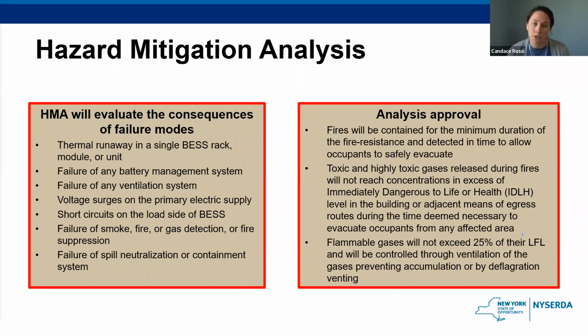So here we have the hazard mitigation analysis, which is only required for energy storage technologies that were not listed in that initial scope, when more than one technology is provided in a room or enclosed area, or where allowed as a basis for increasing the maximum allowable quantities. So we'll get into that in a few slides. But basically, any lithium ion system over 600 kilowatt hours will be required to perform this analysis. So this study is done to evaluate the consequences of failure modes. These are usually done by an engineering firm for the town to determine the best approach on how to handle a failure. The analysis will evaluate the consequences of the following failure modes.